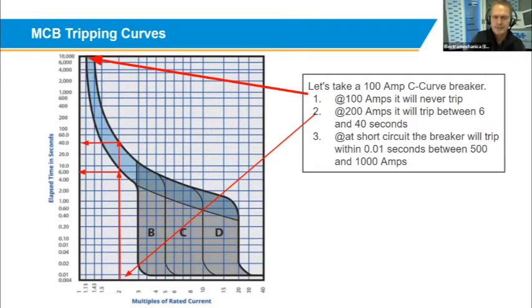It's much appreciated. Then, if you take this same 100 amp C-curve circuit breaker, and what we say is it's short circuit. It will trip within 0.01 seconds, and what it means is that we're getting to the IN rating of the circuit breaker. So we said a C-curve IN rating is between 5 to 10 times. So between 500 amps and 1,000 amps, this circuit breaker will come out on short circuit.